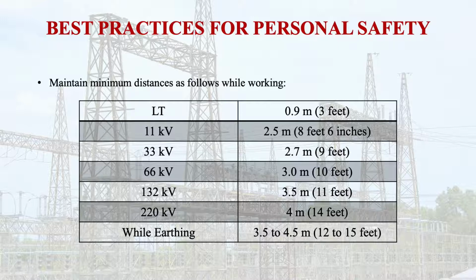For 11 kV, the minimum distance is 2.5 meter or 8 feet 6 inches. For 33 kV, it is 2.7 meter or 9 feet. For 66 kV, 10 feet. For 132 kV, 11 feet. For 220 kV, 14 feet or 4 meter.